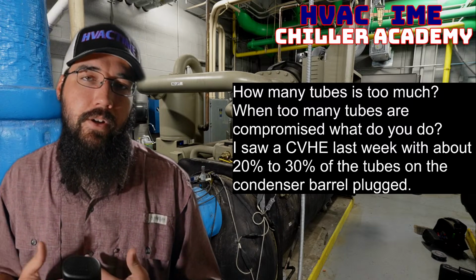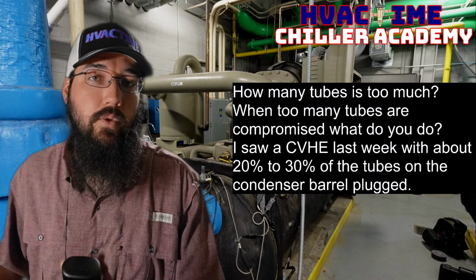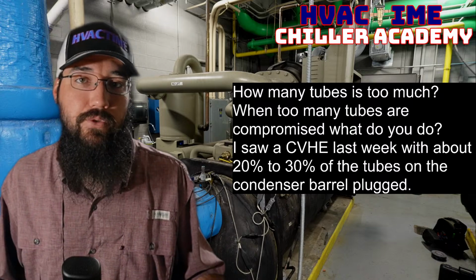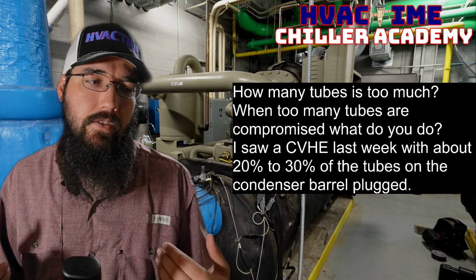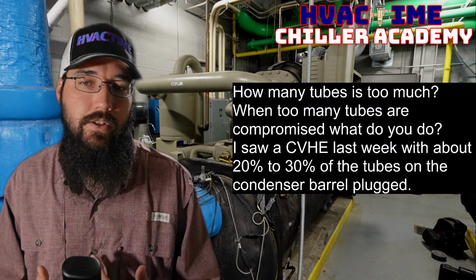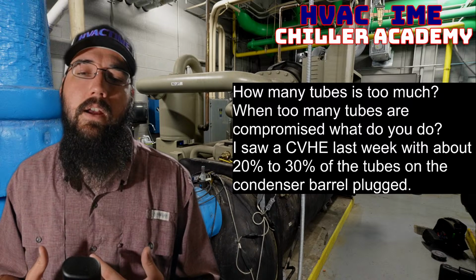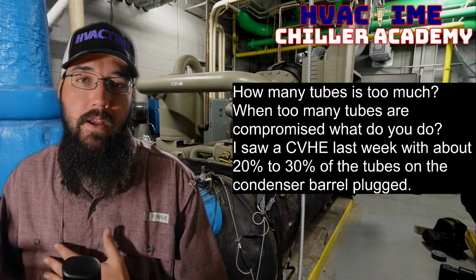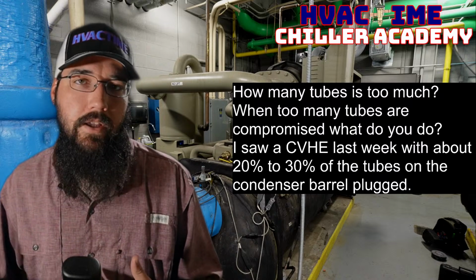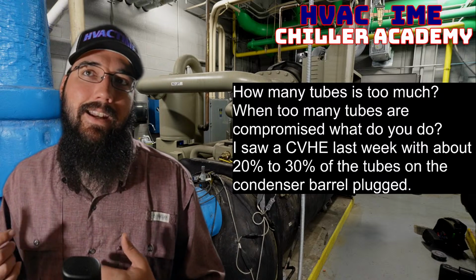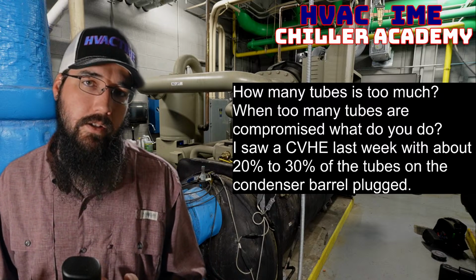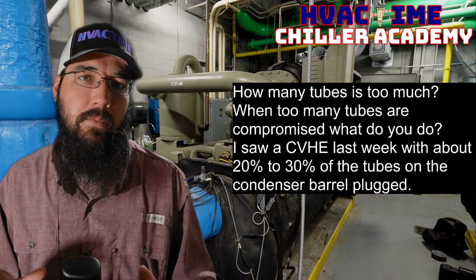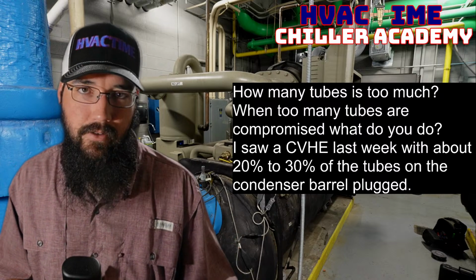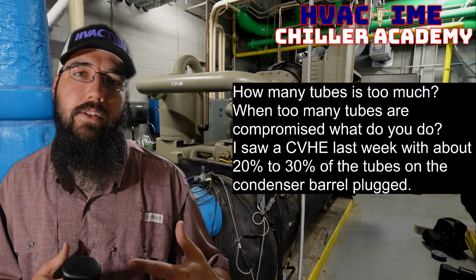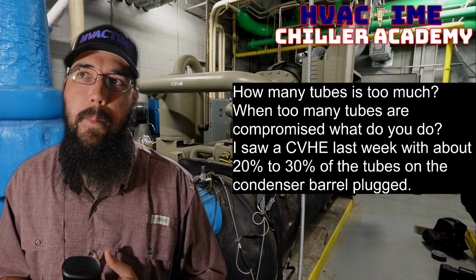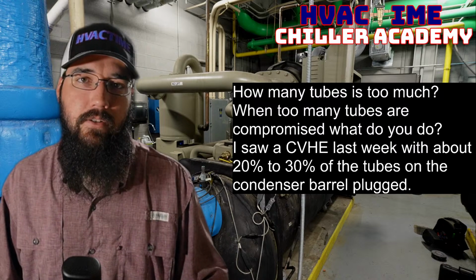Now, depending on your circumstances, it could be a situation where it's worth considering just an all-out replacement. If you've got an extremely old machine, and especially from an efficiency standpoint, it just ain't cutting it anymore, it may be worth, instead of trying to pay for a really expensive retube, to just go ahead and replace the machine, or plan to do that. And at least if you can still get it to run and maintain some kind of operation but it hasn't completely failed, it gives you the opportunity to address that chiller before a complete failure happens. Meaning, get it ordered, get it replaced.